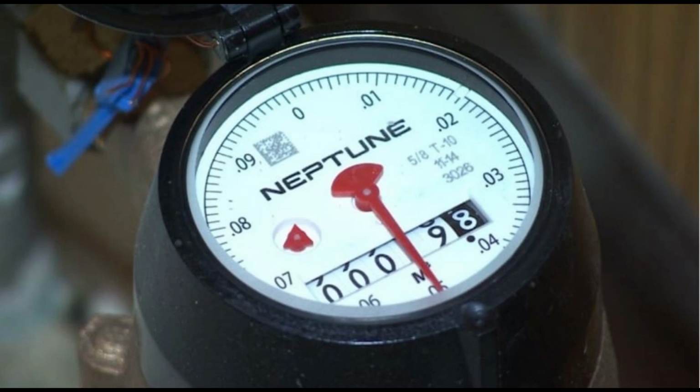Compound meters have two measuring elements and a check valve to regulate flow between them. At high flow rates, water is normally diverted primarily or completely to the high flow element. The high flow element is typically a turbine meter. When flow rates drop to where the high flow element cannot measure accurately, a check valve closes to divert water to a smaller element that can measure the lower flow rates accurately. The low flow element is typically a multi-jet or PD meter. By adding the values registered by the high and low elements, the utility has a record of the total consumption of water flowing through the meter.